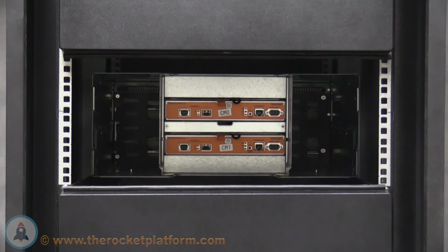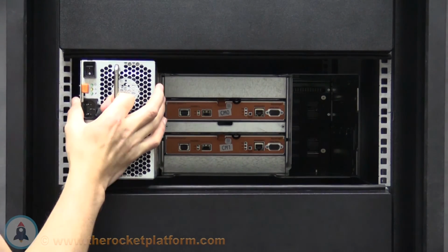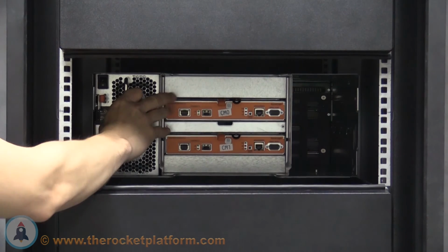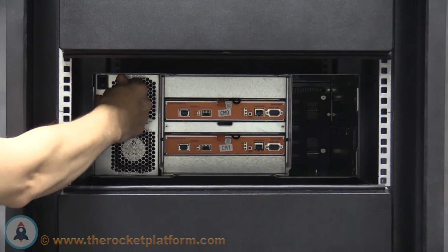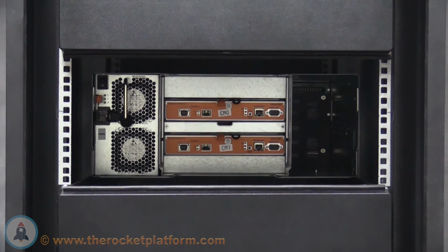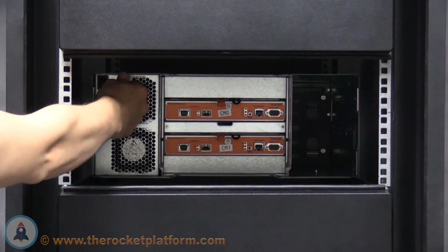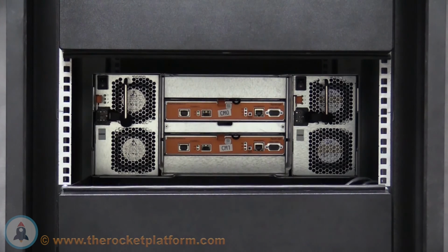After the controllers have been replaced, you will need to insert the power supplies. Take a power supply and insert it into one of the slots, ensuring that the connector pins are facing toward the center of the chassis and the orange tab is situated in the top left-hand side. Push the supply back until you hear or see the orange tab click into place. Pull back on the metal bar without releasing the locking mechanism. If the supply stays in its slot, then the supply has been properly seated. If the supply moves around in the slot, then the supply has not been properly seated and must be reseated. Repeat this process with the other supply.